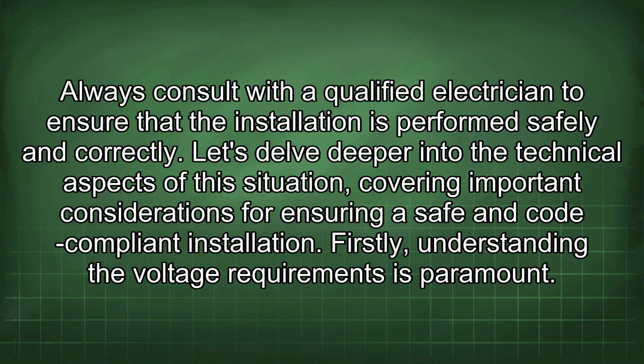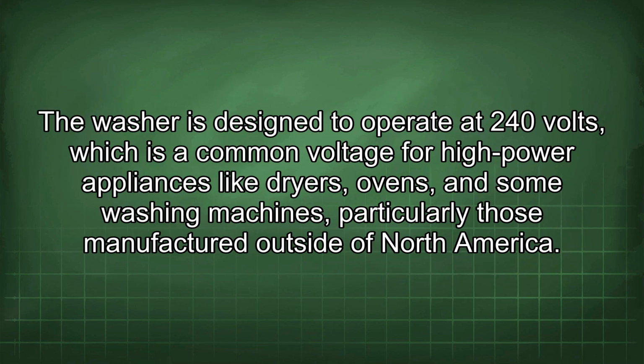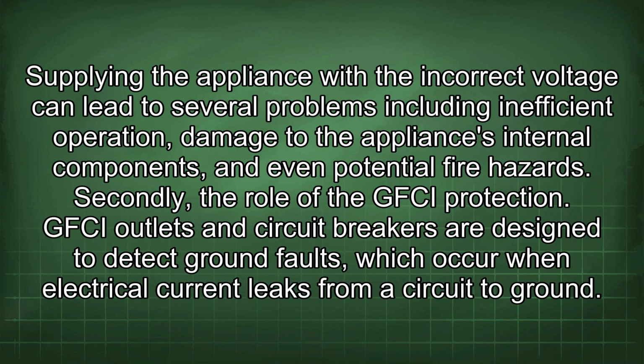Let's delve deeper into the technical aspects of this situation, covering important considerations for ensuring a safe and code-compliant installation. Firstly, understanding the voltage requirements is paramount. The washer is designed to operate at 240 volts, which is a common voltage for high-power appliances like dryers, ovens, and some washing machines, particularly those manufactured outside of North America. Supplying the appliance with the incorrect voltage can lead to several problems, including inefficient operation, damage to the appliance's internal components, and even potential fire hazards.